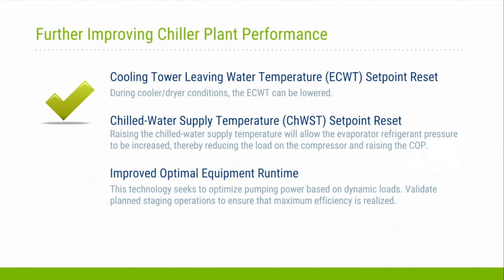And just some things that we noted based on the performance. The cooling tower entering condenser water temperature never was operated any lower than 65 degrees. Obviously, in this climate location, the higher wet bulb temperatures have some impact. During the summer months, you're never going to get down to 65 degrees anyway. But there were times in the cooler months when they could have attained lower condenser water temperatures, but the software, for whatever reason, did not do that.